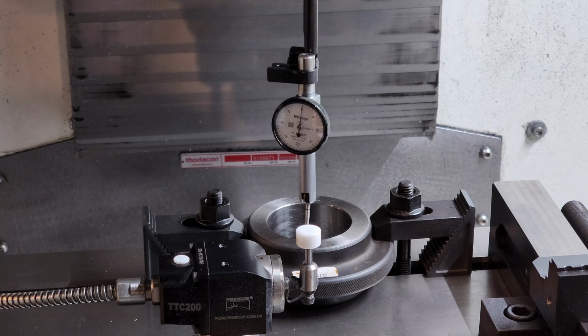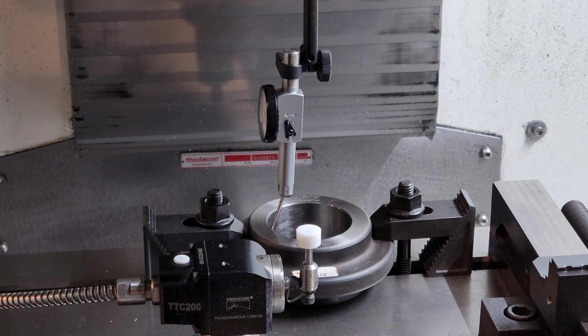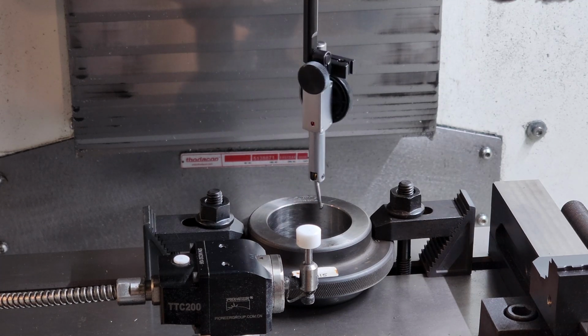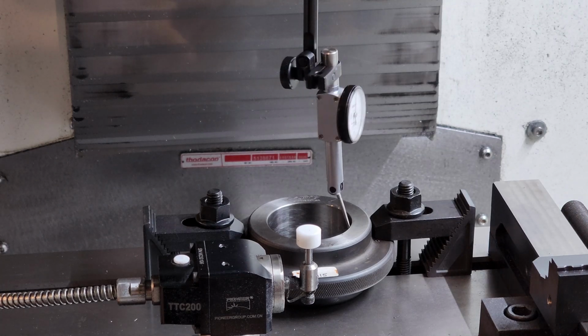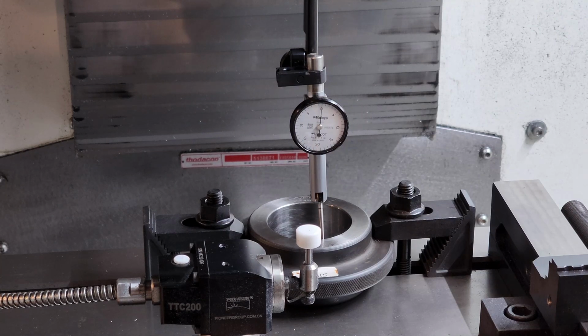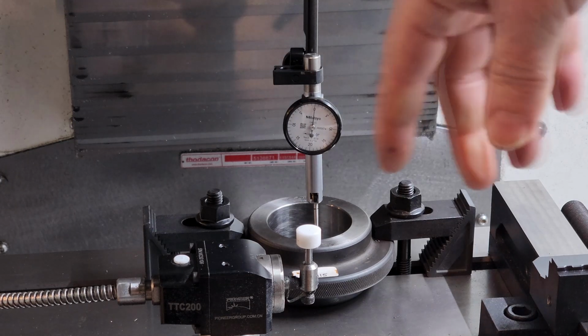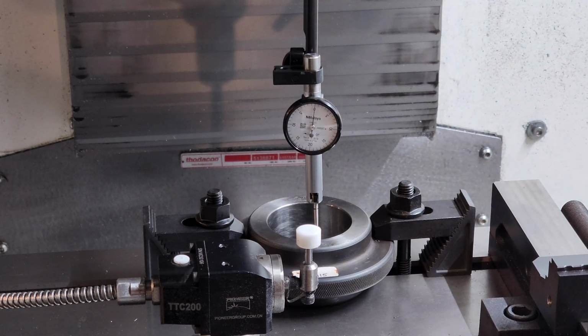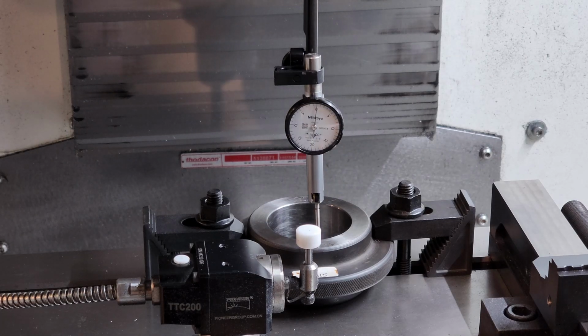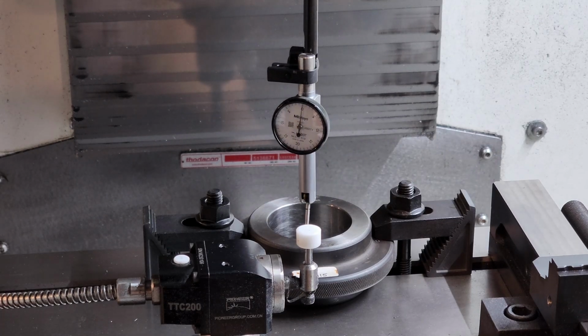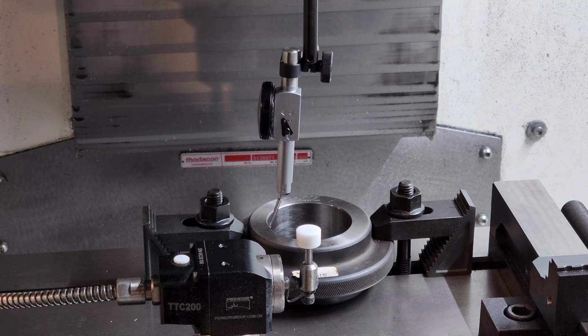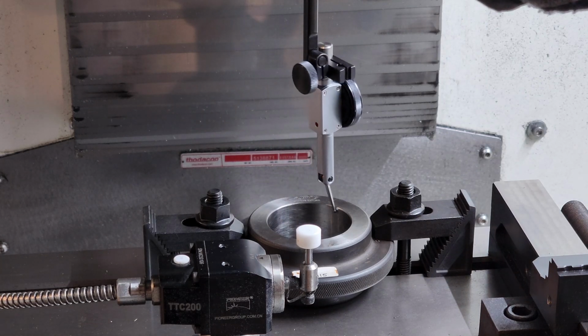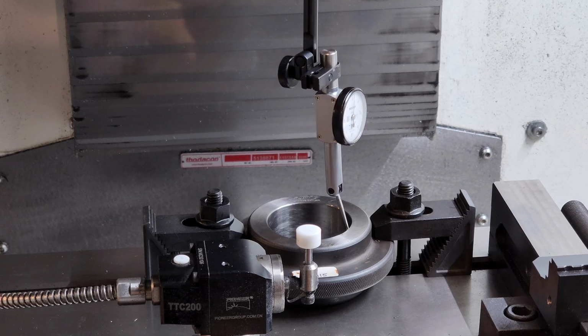First, rotate the spindle, alternating the position of the indicator between the left and right sides of the gauge. As you do this, adjust and find the 0 position in X. Next, rotate the spindle to the front quadrant and adjust in Y until the indicator reads 0. Readjust as needed until the indicator reads 0 in all 3 positions. Now as you sweep the indicator around the ring gauge, it should read 0 throughout. The spindle is now aligned with the center of the ring gauge and we can proceed to the first calibration.